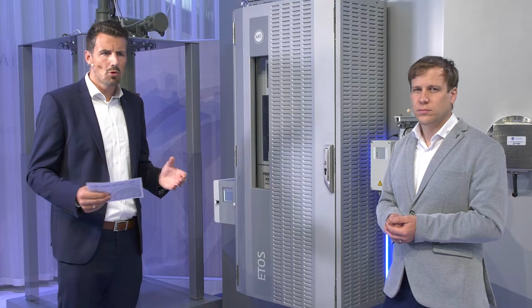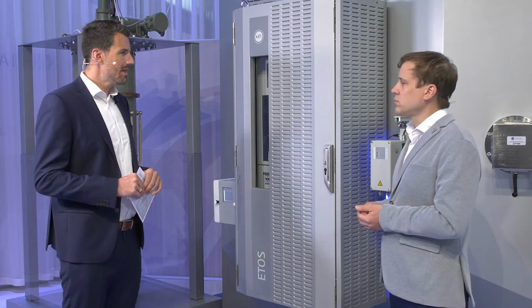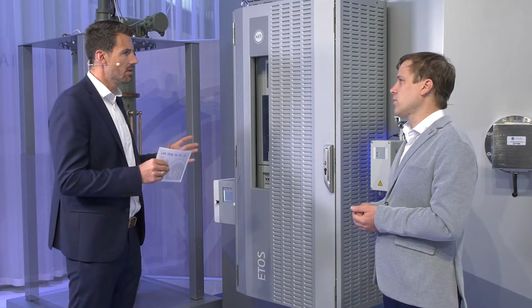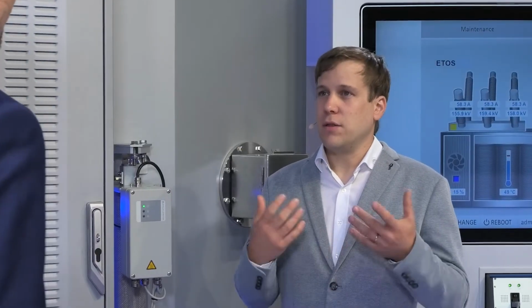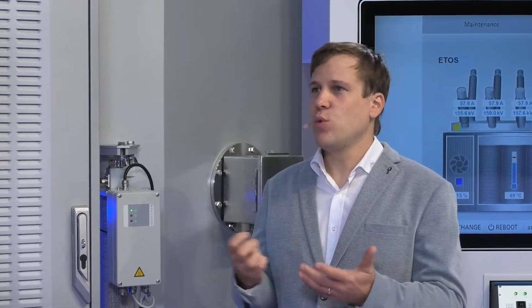Okay. Talking about the bushings, I think it's obvious and very well known that many transformer failures result from defective bushings. Peter, what possibilities do we have in terms of monitoring high voltage bushings? Well, as you said, the bushing monitoring system, our MSense BM, would be the brand name here. This system is connected directly to the measurement tap of the bushing. So we need the measurement tap, and then we can read the values from there. With this information, we can do the C1 capacitance monitoring and also the tan delta. Therefore, we require the reference system from the incoming line for that respective bushing. Okay, also a solution available to monitor high voltage bushings. Exactly.